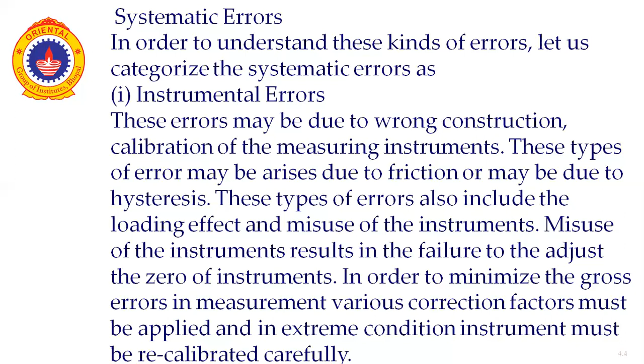Now, systematic errors. In order to understand these kinds of errors, let us categorize the systematic error. First one is instrumental error. These errors may be due to wrong construction or calibration of the measuring instruments. These types of errors may arise due to friction or hysteresis. They also include the loading effect and misuse of the instrument. Misuse of the instrument results in failure to adjust the zero of instruments. In order to minimize this error in measuring, various correction factors must be applied, and in extreme conditions, the instrument must be recalibrated carefully.